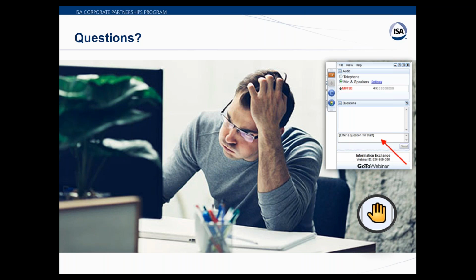But after you, as Roy said, do three tests, 1, 2, 3, you'll start to see maybe a pattern. Is it random? Is it going up and down? Or are you seeing a trend? If you're seeing a bad trend, it maybe failed on the second test, and you adjusted it and it's still drifting, you need to tighten up your frequency. But most of the time, people are conservative, they're over-calibrating.